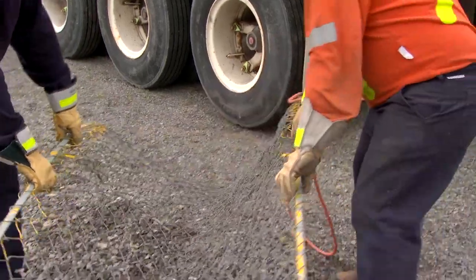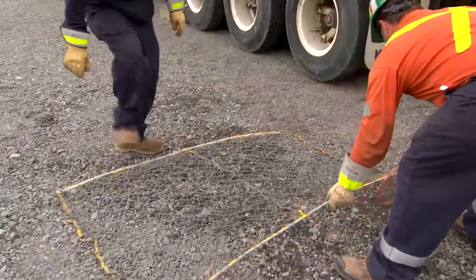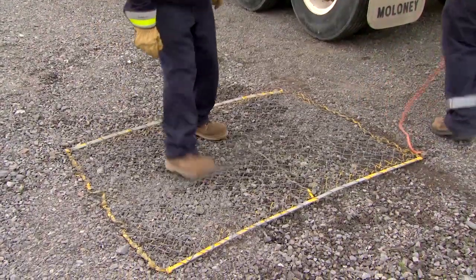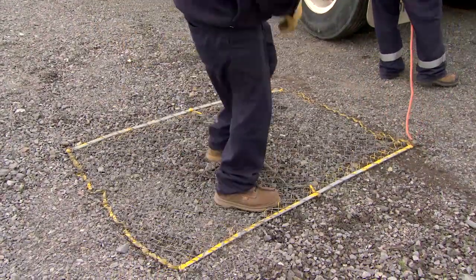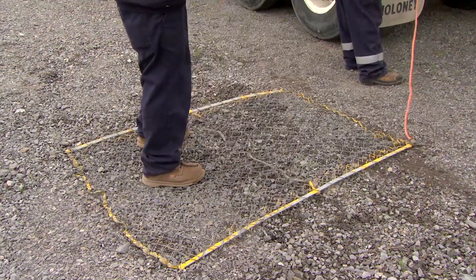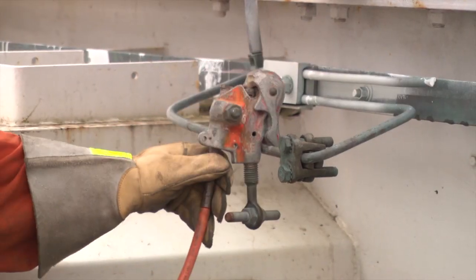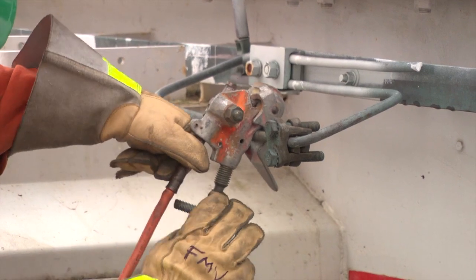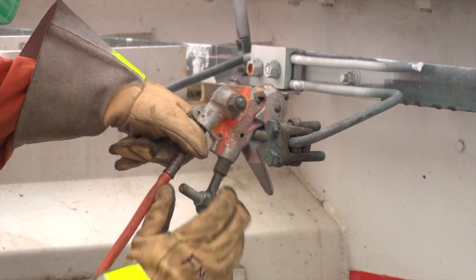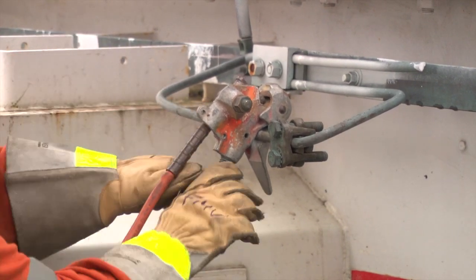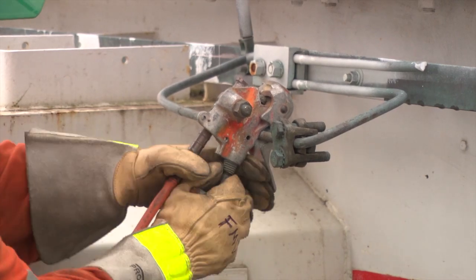After installing the driving mechanism, open up the switch with the hand crank to ensure that there is no binding on the mechanism drive and that the switch is operating freely. Install the high voltage switch grounding mat, connecting the ground lead to the MUS ground bar. Switching mats should not be installed during erection of the mobile because it creates a tripping hazard.